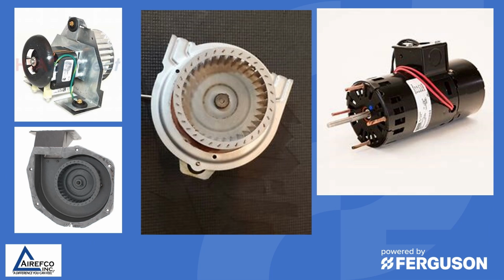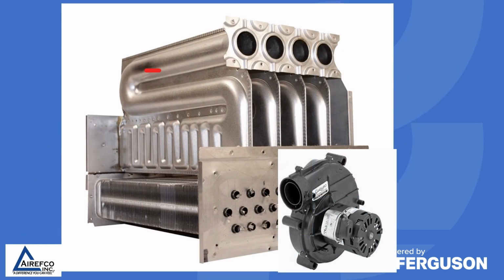Most of your gas furnaces today have an induced draft motor, and they come in all kinds of shapes and sizes, but when you're working on a furnace, you need to understand how they operate and keep them operating properly. So the inducer motor on a gas furnace has two purposes.